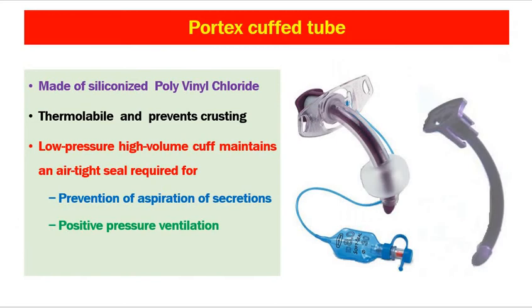Now let's come to the Portex cuffed tracheostomy tube, which is made of siliconized polyvinyl chloride. It is thermolabile — slightly stiff during insertion but becomes more malleable and softer once inside the body — and it prevents crusting. Being a cuffed tube, it can be used as the first tube during tracheostomy, can be used during positive pressure ventilation, prevents aspiration of secretions, and provides an airtight seal for ventilation. The outer part contains a 15 mm connector to be fitted to ventilators.